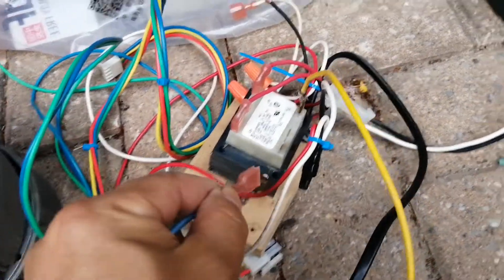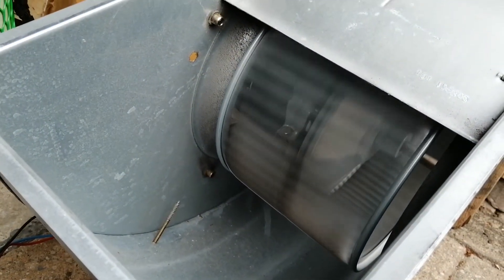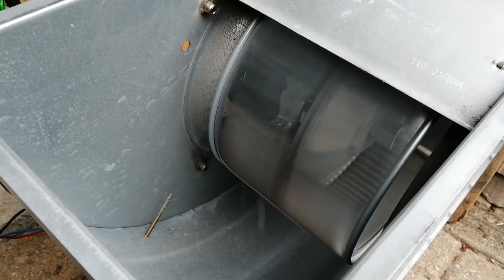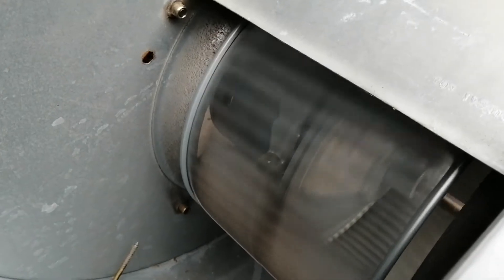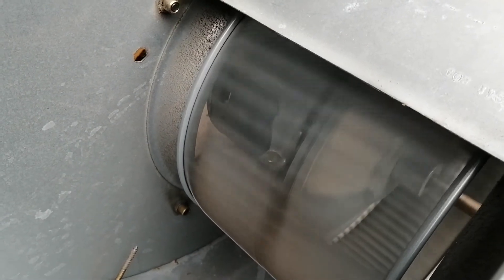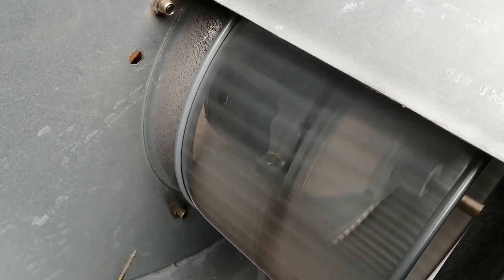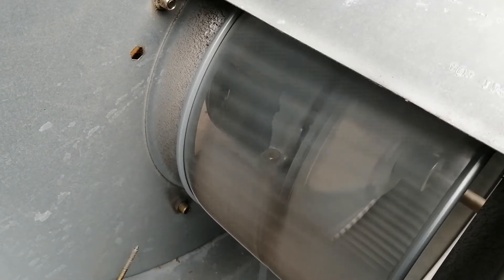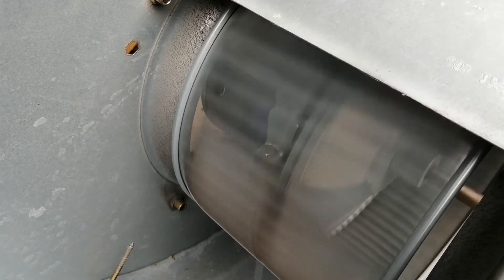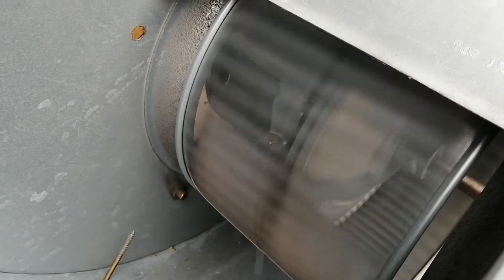When I connect the power plug, you'll see the fan spinning — it is unstable, running up and down, but it's continuous running. So that proves this ECM module is working.